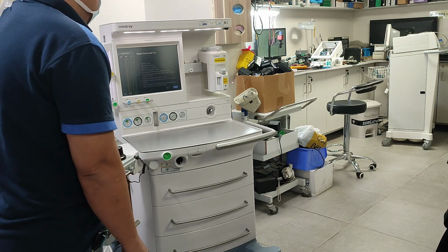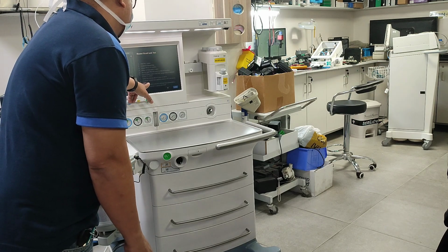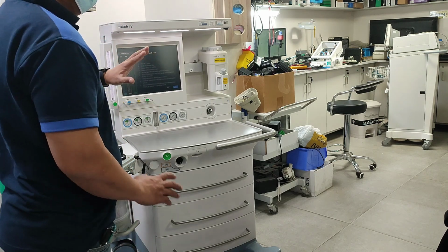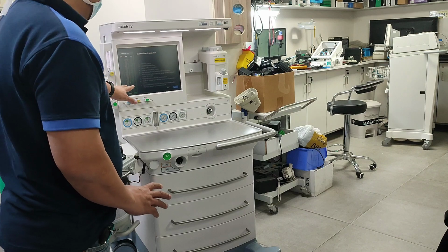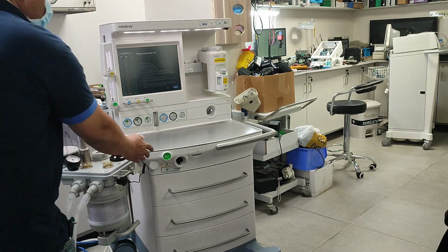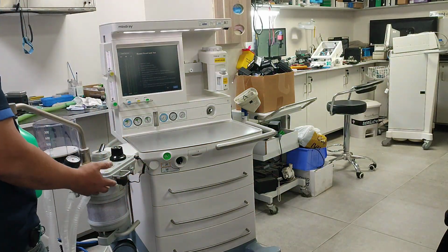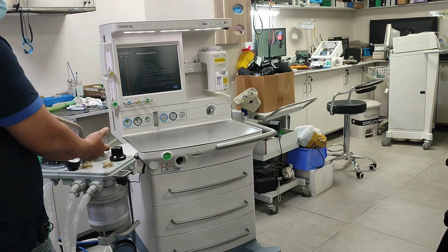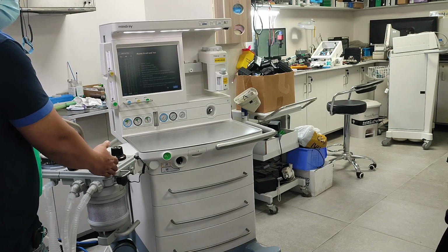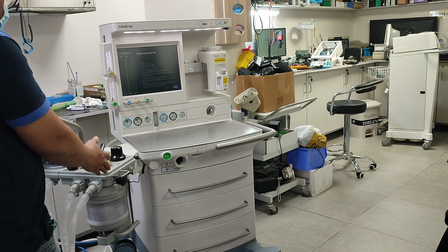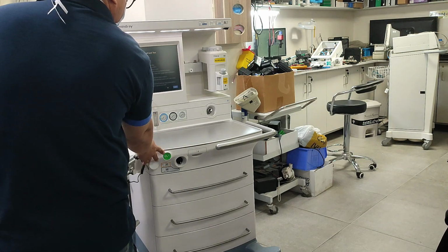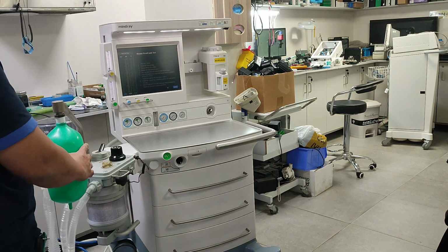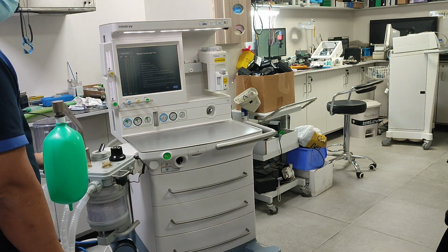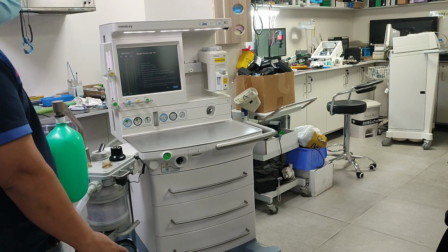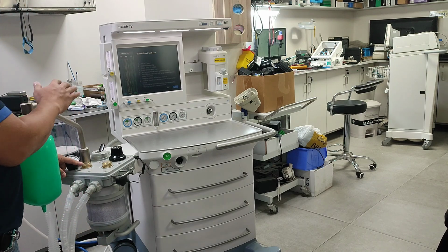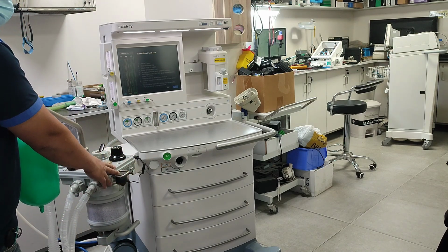So the bellows is not moving. If the bellows moves, turn the machine power off and call the service engineer. So this is the issue. If this moves while you are pushing this button, and the bellows also goes up, it means you have an issue with the patient module. This time we push the O2 flush, so it will not go down. If this pressure gauge goes down, it means there is a leak in your patient module.